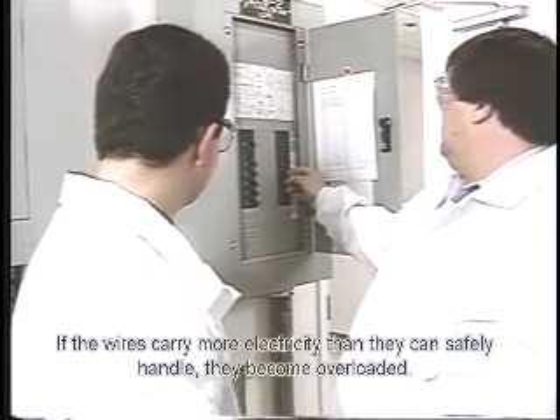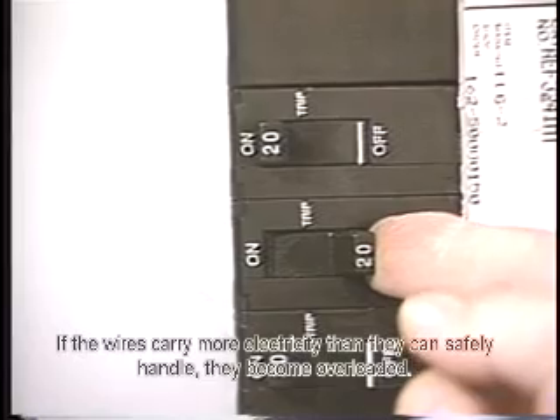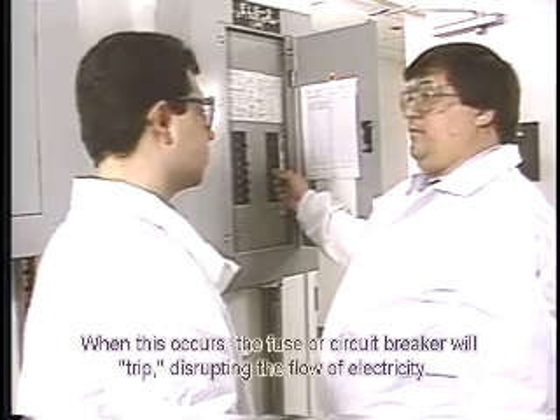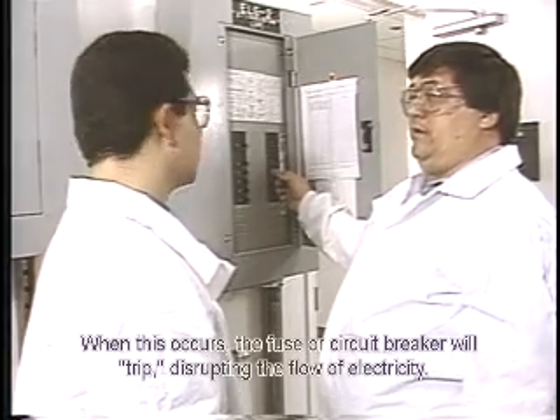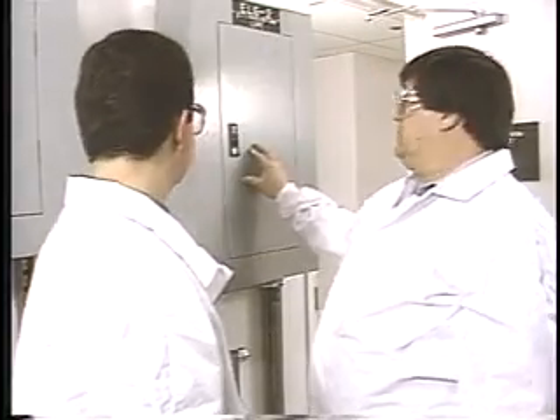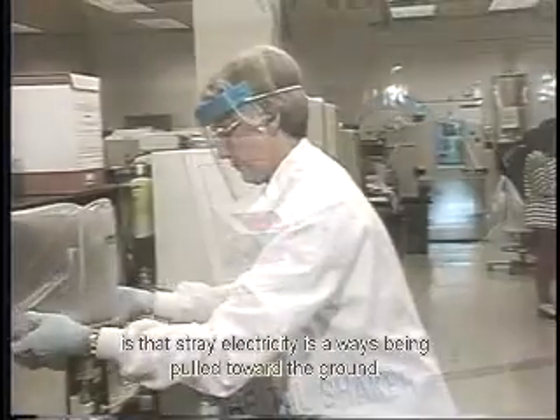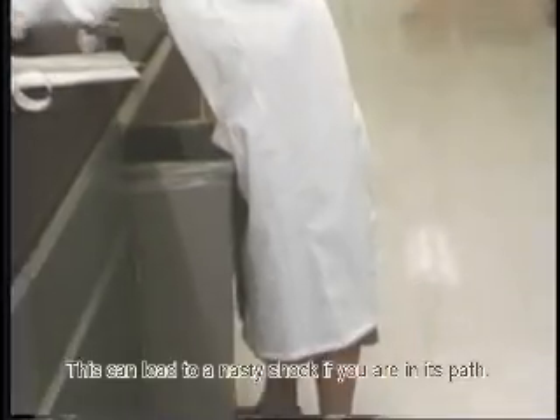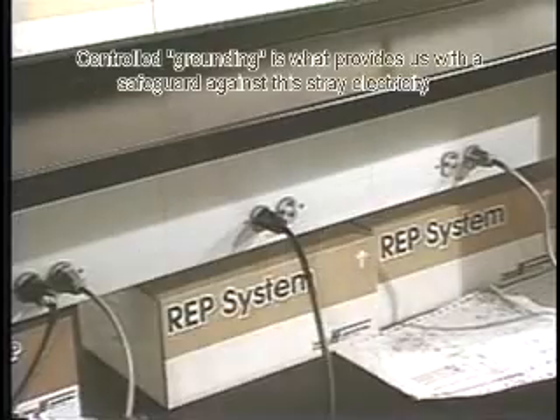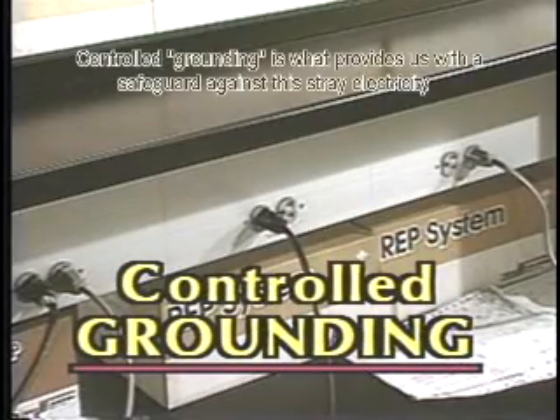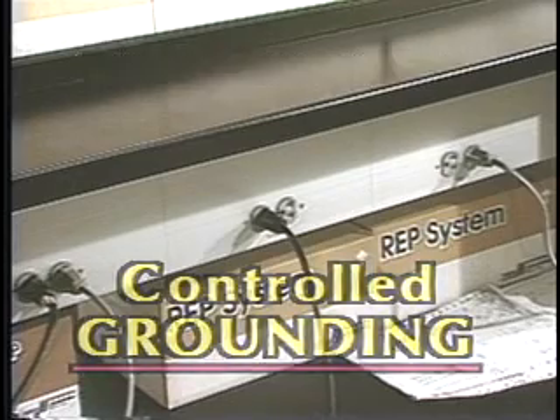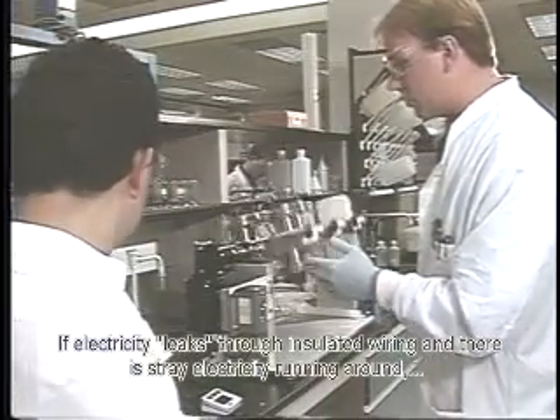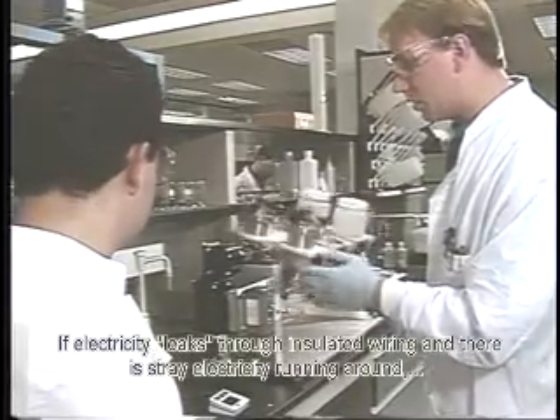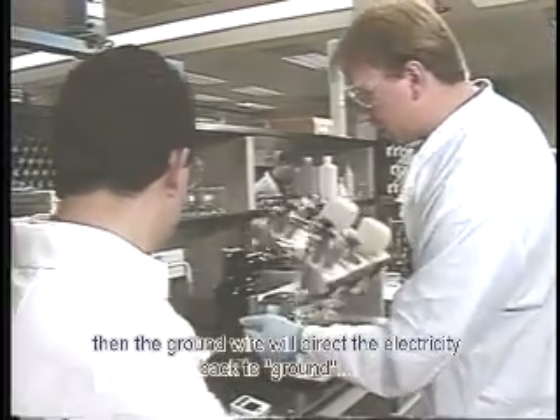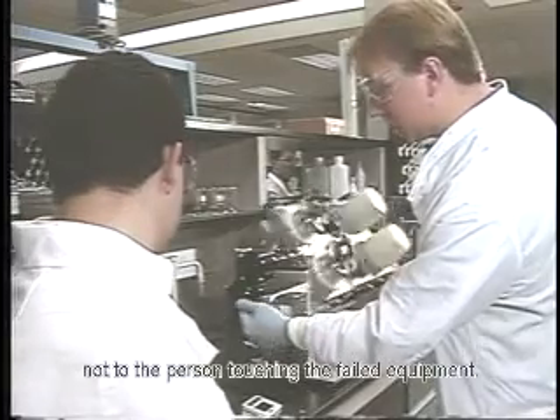If the wires carry more electricity than they can safely handle, they become overloaded. When this occurs, the fuse or circuit breaker will trip, disrupting the flow of electricity. Another important principle to remember is that stray electricity is always being pulled toward the ground. This can lead to a nasty shock if you're in its path. Controlled grounding is what provides us with a safeguard against this stray electricity. If electricity leaks through insulated wiring and there's stray electricity running around, then the ground wire will direct the electricity back to ground, not to the person touching the failed equipment.